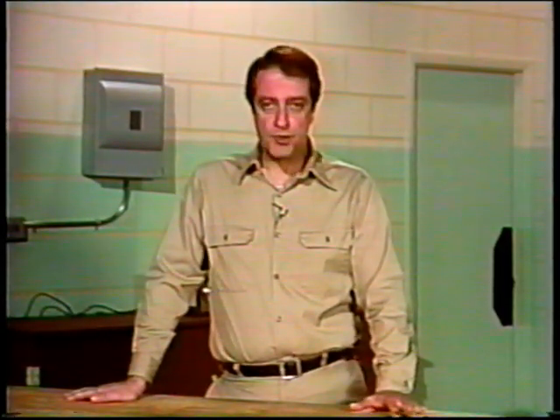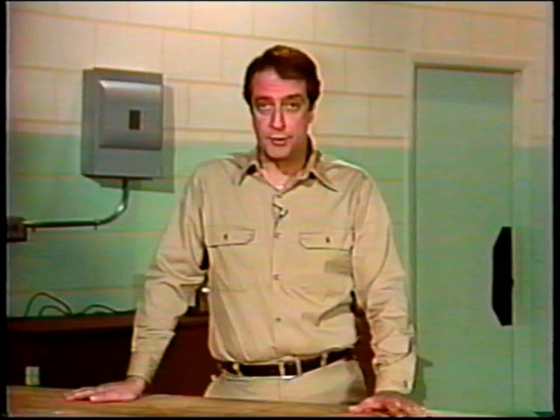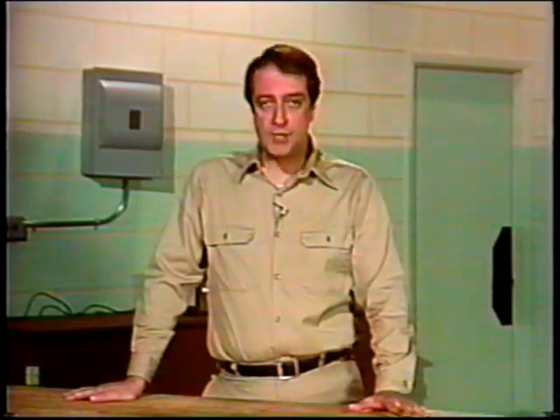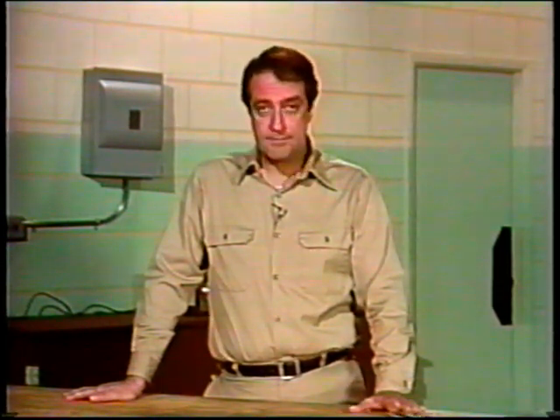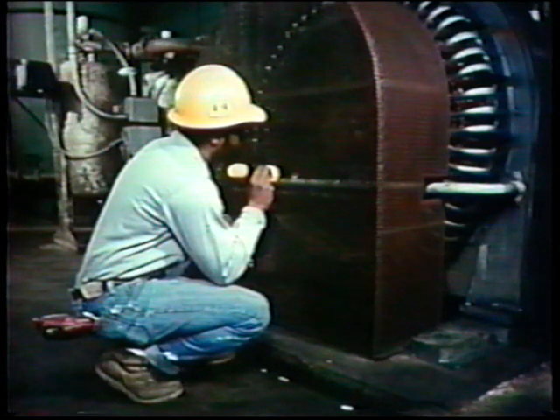Grounds, opens, and shorts are also common problems found in synchronous motors. These problems can cause malfunctions in both the stator and the rotor of a synchronous motor. Before testing a motor for these problems, the motor must be de-energized and then tested to make sure that it is completely de-energized. Next, the motor should be visually examined for any indication of where the problem might be located in the motor. After visually examining the motor, the protective screen can be removed and the motor can be tested.